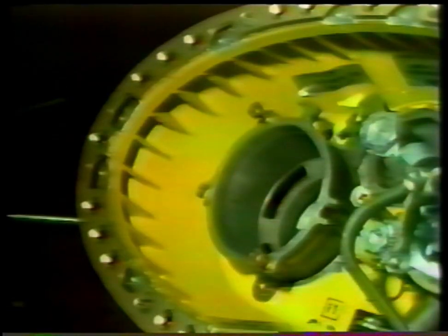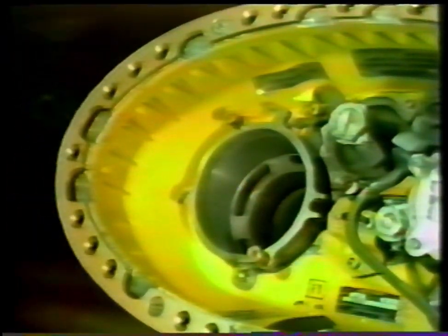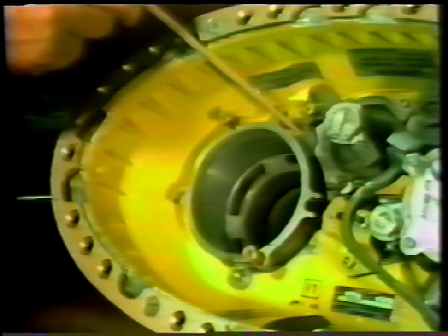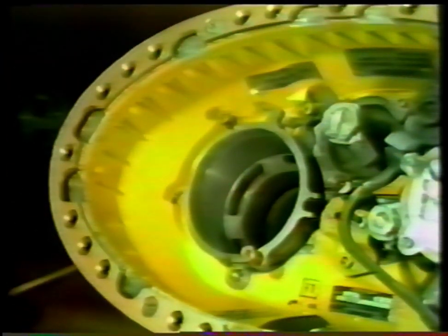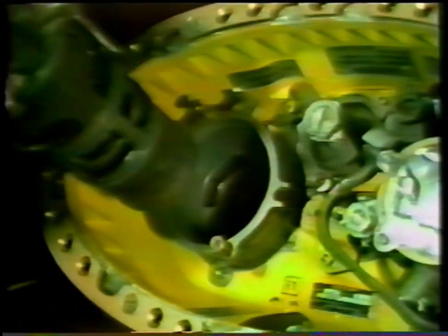To illustrate this, as the pump is being reinstalled, if the sleeve is pushed in, it will unseat and could cause a major spill. The bolts are out of alignment and the pump won't go in all the way. To remedy this, you must remove the pump to reseat and lock the sleeve to stop the fuel flow. To reset the cam, here where it is against the sleeve, you must use a screwdriver to lift the cam over the ramp on the sleeve. Pulling down on the sleeve will then reseat the valve and fuel flow will stop. Now you can replace the pump body in the normal manner.